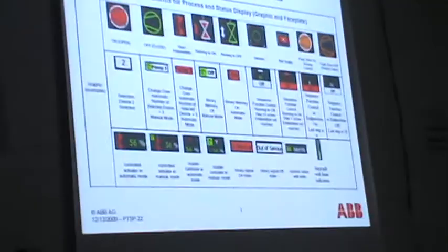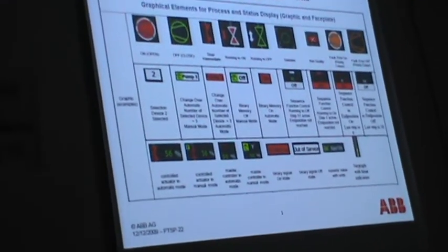So what about when the flow reduces? When the flow reduces, the last one which was started, say you selected pump 3 and it is started now, if the flow reduces, again this same pump will stop. Again, whichever was the last pump started will get stopped.